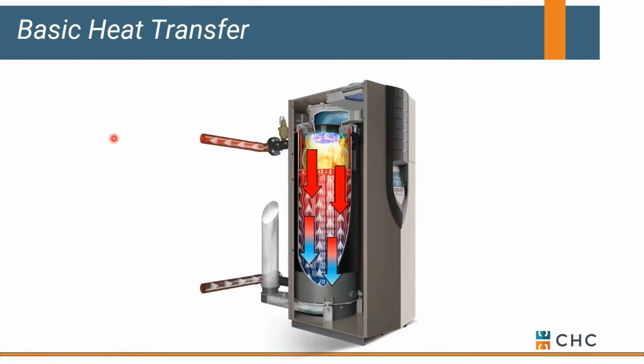The only difference is, instead of using steam or hot water, we're burning natural gas typically. You might also be burning propane or #2 fuel oil, depending on your burner type. But typically it's natural gas. Sometimes it's all electric, all choices. But keep in mind, it's nothing more than a fancy heat exchanger. On the system side, we're bringing in cold water, we're circulating around our heat exchanger, which happens to contain 2,500 degree flue gas, and we're simply heating that water up. So it's coming in cold, it's leaving warm, and headed out to our system, where we're either running it through fan coils or VAVs or maybe a heat exchanger for some type of process. But all we're doing is transferring heat in a boiler.